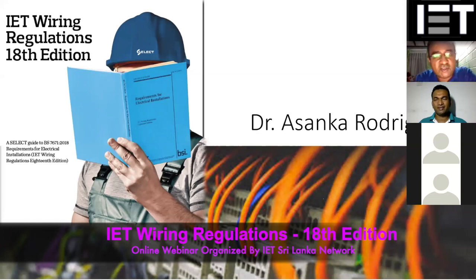Thank you, Doctor. Next question is, how to install SPD to a single phase circuit? As I said, that will depend on whether you go for a TN system or a TT system. In the TT system, you have to have the 1+1 arrangement. That is, you have to have live to neutral and neutral to earth. That is a requirement. For example, if I use live to neutral as 25 kiloampere, the neutral to earth should be 50 kiloampere. If I use live to neutral as 12.5 kiloampere, then the neutral to earth should be 25 kiloampere. But in the TN arrangement, you can go with the 1 plus 1, or you can go with the 2 plus 0.